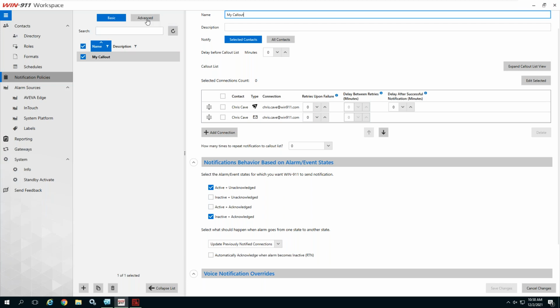And a push report is basically a way of automating a tag. You could tell the tag to trip at the same time every day. That alarm would basically trigger a notification policy, and that notification policy is basically just saying push out this report to someone. So it's not necessarily an alarm notification in this case. Instead, you're using an alarm to trip a report to be able to push it out every day automatically.